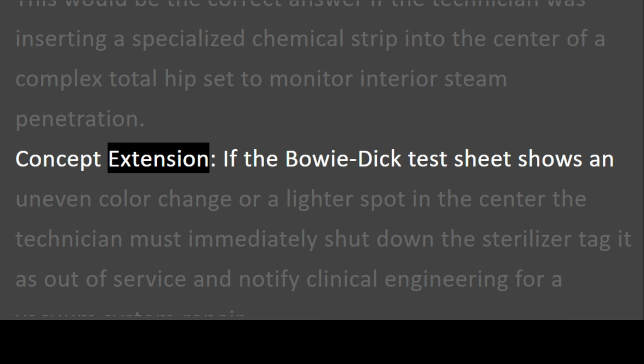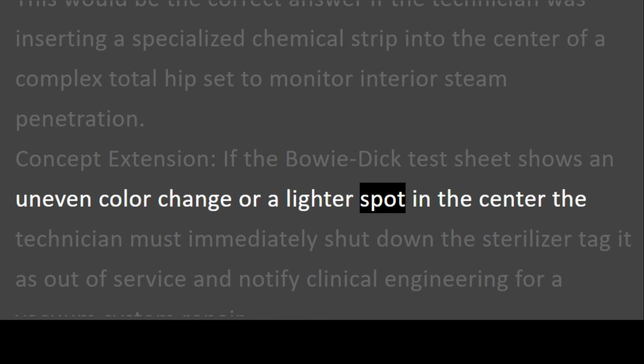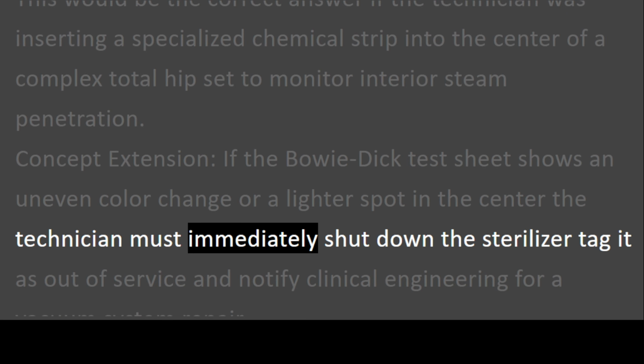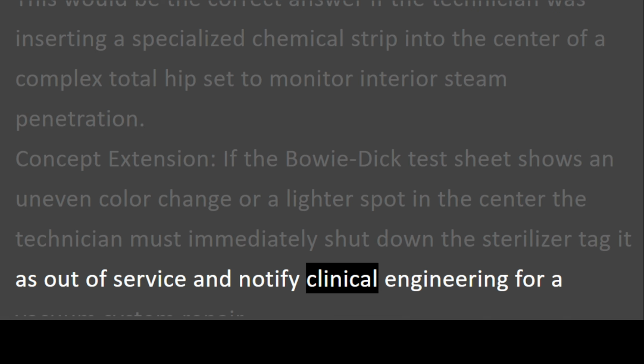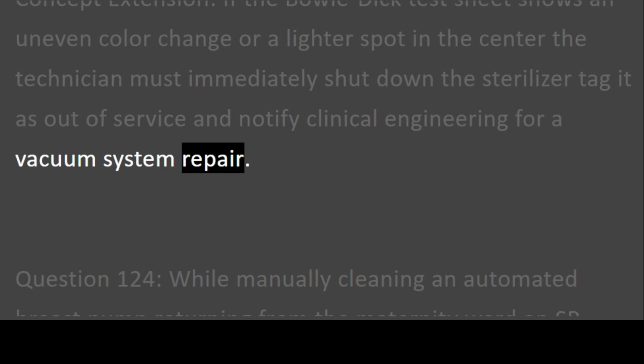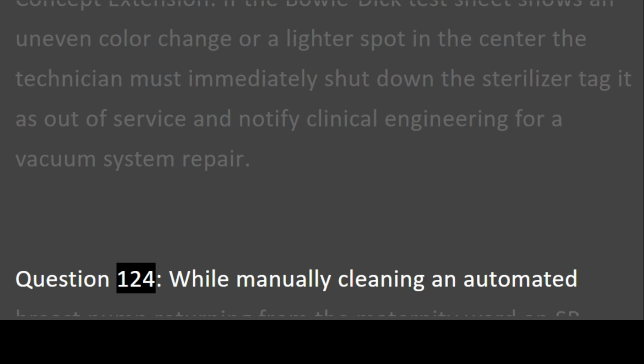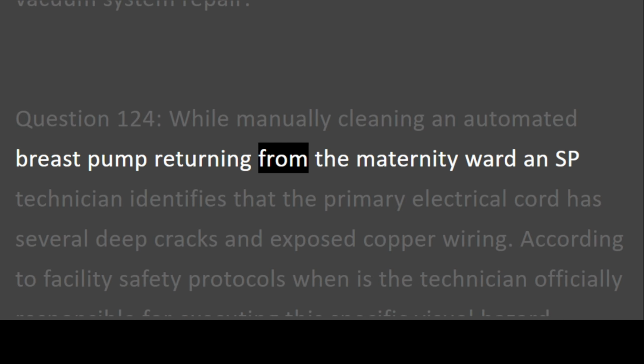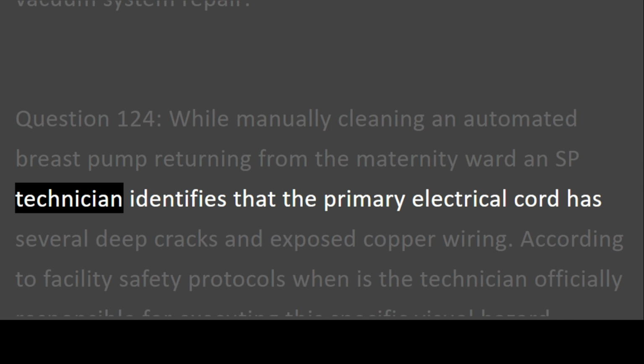Concept extension. If the Bowie-Dick test sheet shows an uneven color change or a lighter spot in the center, the technician must immediately shut down the sterilizer, tag it as out of service, and notify clinical engineering for a vacuum system repair. Question 124.